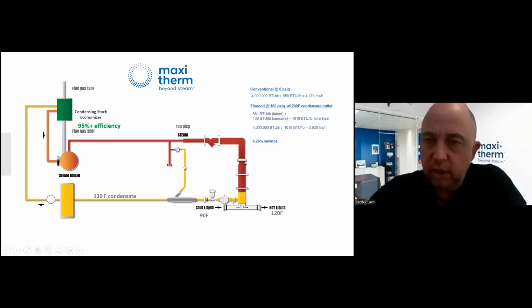Now, in my previous video, I showed those numbers. We compared a conventional design with a 1/3, 2/3 steam control valve operating at 6 psi, because you always have a pressure drop at your steam control valve at full load. Comparing with 100 psi steam and condensate leaving at 200 Fahrenheit, the benefit was 6.26% less steam to do the same job.